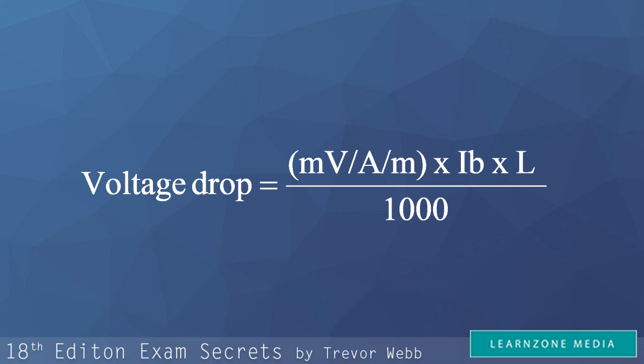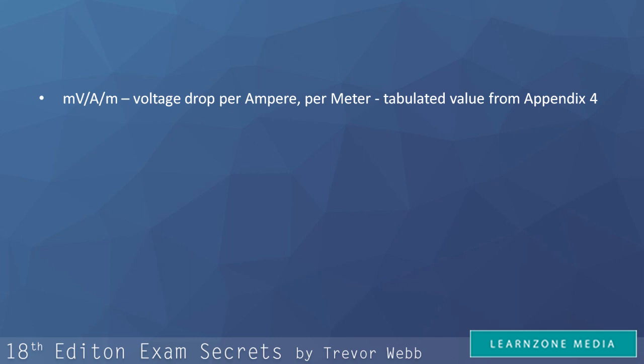Right, so let's talk about this formula for just a little bit. What you need to know is that millivolts per amps per metre stands for voltage drop per ampere per metre, and this is a tabulated value that is specific for each cable listed in appendix 4.